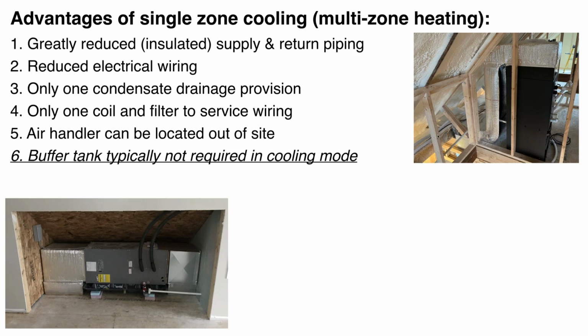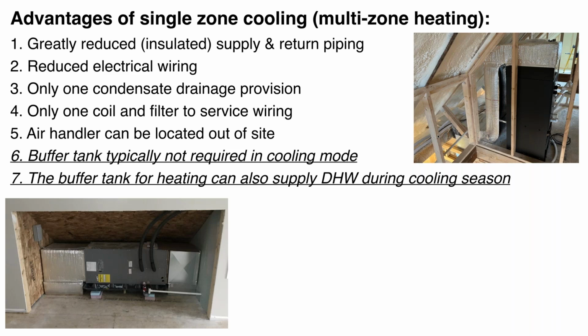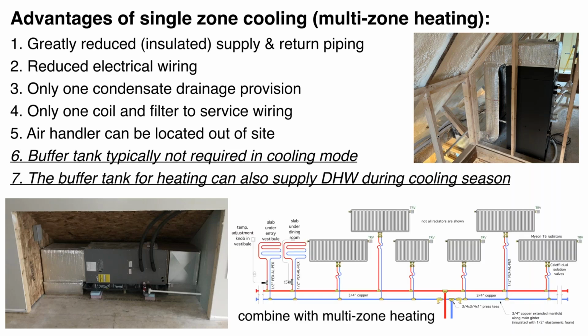But the trending, especially today with both air to water and water to water heat pumps, is inverter compressors. And the nice thing about that is the machine, the heat pump, can actually adjust its compressor speed based on maintaining a certain leaving water temperature. So now you can actually have a heat pump that can reduce its cooling capacity and match a smaller air handler. The other nice thing about that is that since we don't need a buffer tank in cooling, we can use a buffer tank or a reverse indirect water heater, and we can provide both cooling and domestic hot water heating in summer. Now, we can't do both at the same time. We have to toggle back and forth, and we'll get into some slides on that.